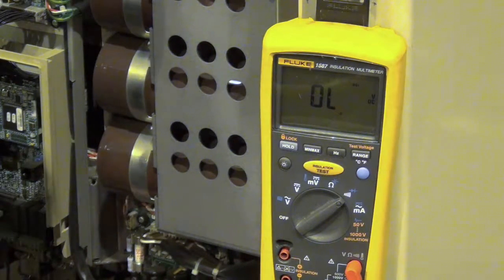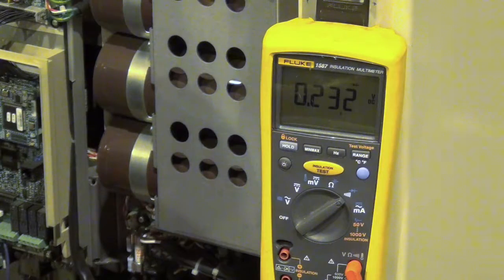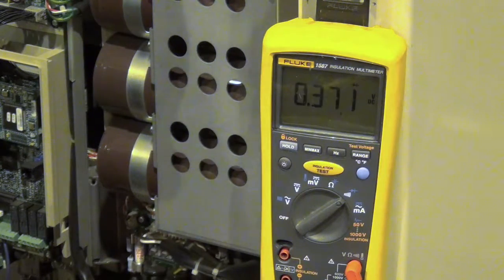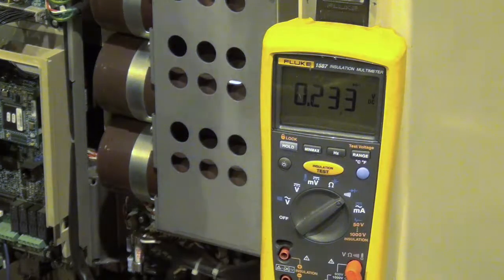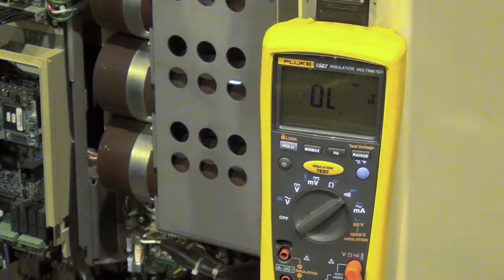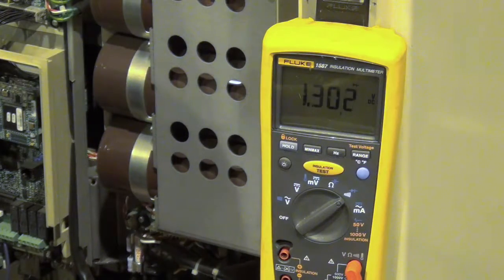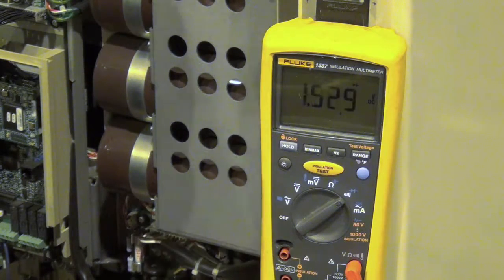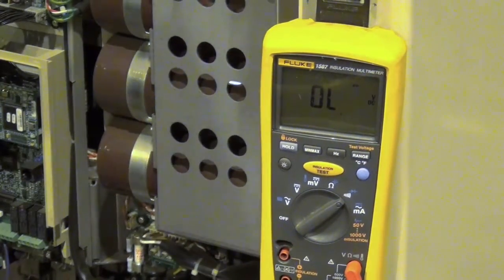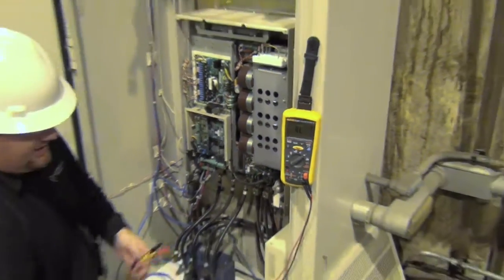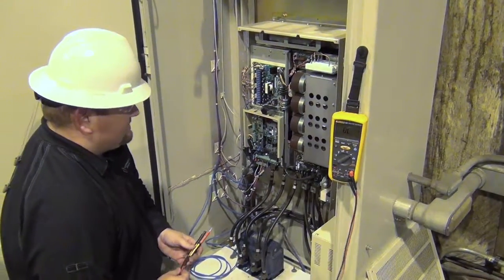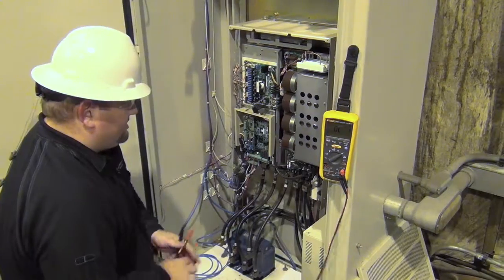Black on plus. Come across. 0.232. 0.232. 0.233. So those show as a diode passing in one direction. We're going to switch our probes. And now we should have our climbing. So 1.3. Picking up 1.6. And 1.8. So that test verifies that the diode and the transistor bank in this particular drive appear in perfectly good condition, quite healthy.